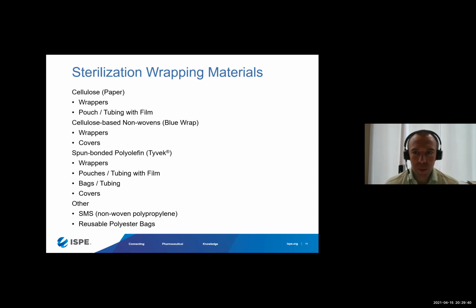I just wanted to point out there are some others out there on the market, something called SMS, which is a 3-layer laminated polypropylene. SMS stands for spunbonded, melt-blown, spunbonded polypropylene. This is, I would say, more comparable to the polyolefin or the Tyvek, so it has some good properties, but I would say there are some limitations to the SMS as well. Other options include polyester bags. These are reusable. Sometimes they have zippers or snaps for closures. Again, these are less prevalent in the industry, and I'll talk through why maybe these are not the best options for sterilization for in-process parts and components.